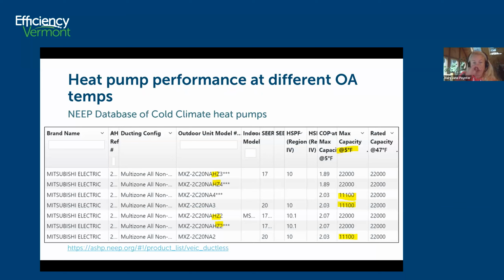So here's a snip from the cold climate database. I picked Mitsubishi units and they're all 20s. I don't have their rated cooling capacity, but I picked their rated heating capacity as all the same, 22,000. But that's at 47 degrees. Well, I don't really care what my unit is putting out at 47 degrees. I want to know what it's doing at 5 degrees. So you can see based on the model, some of them will only give you half capacity at 5 degrees, and some of them will give you full capacity. I'm going to guess that the ones that give you full capacity at 5 degrees are going to cost significantly more than the units that give you half capacity.